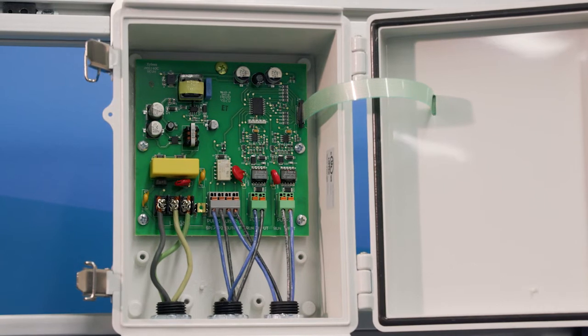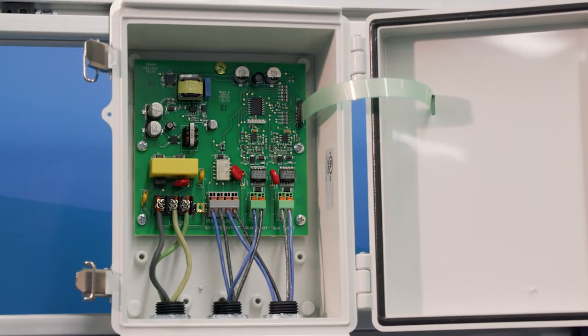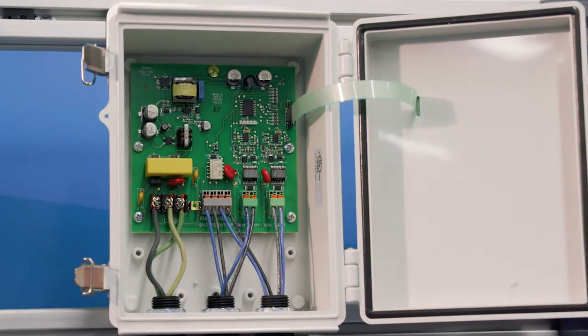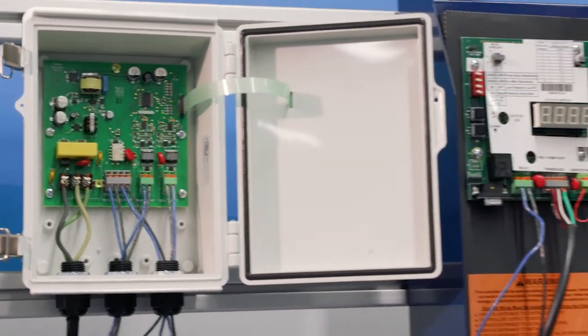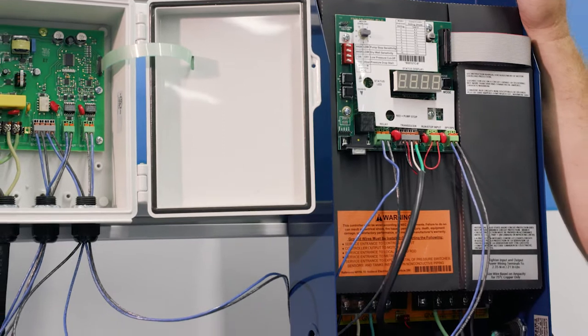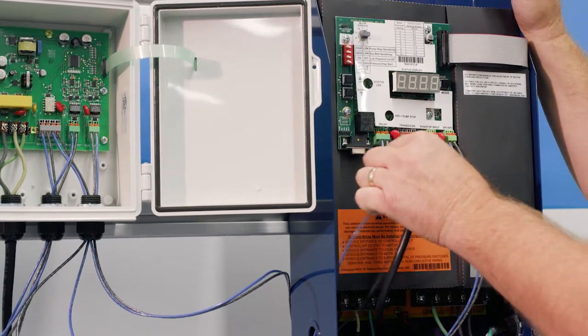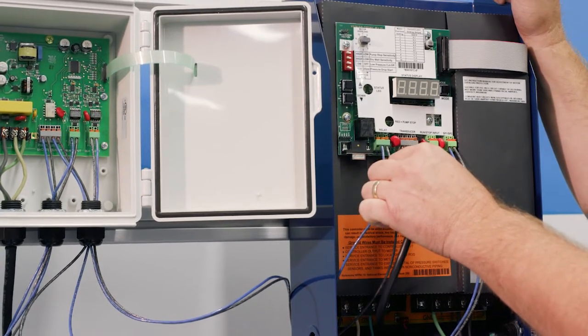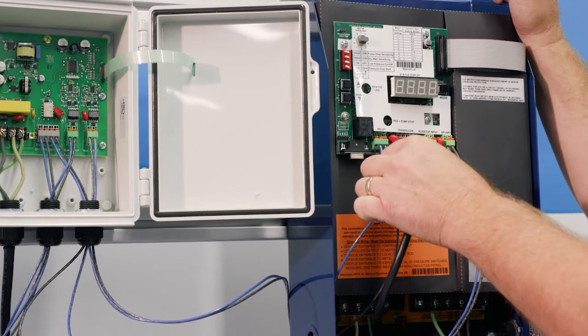So one way to tell, if we're coming up to a job site, we're wondering, how is this thing wired? If we're going to the relay, that's based on runtime. Our alternation is based on runtime. If we're not wired to the relay here, then that's based on elapsed time.